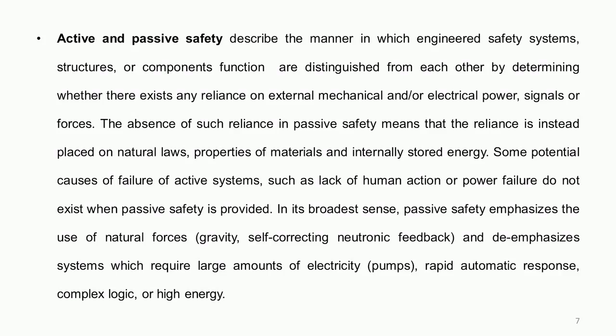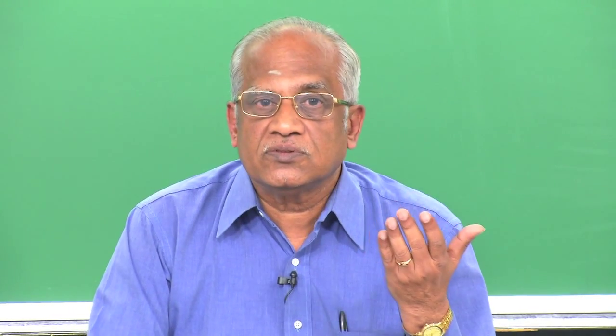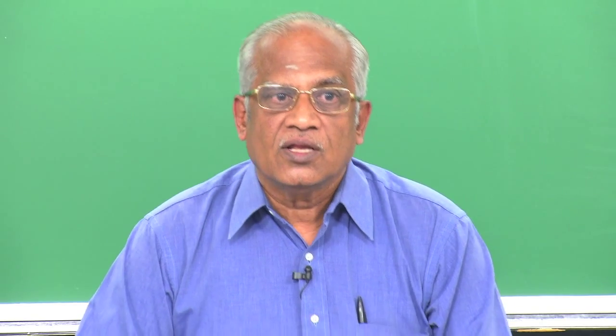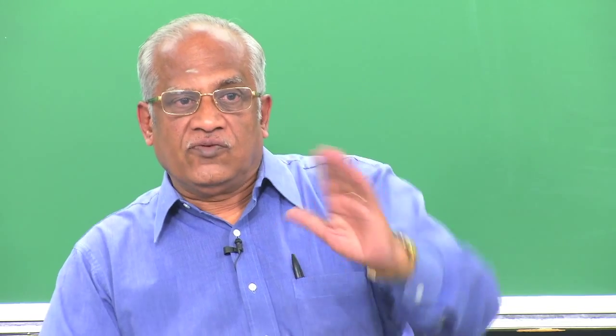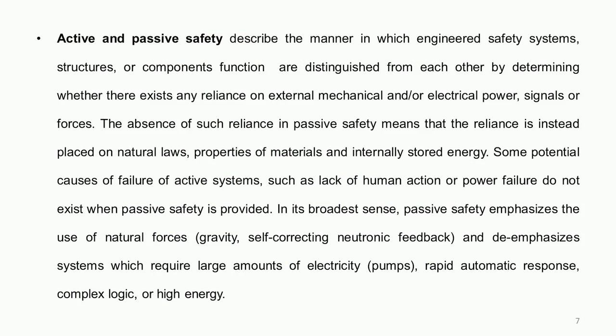A passive safe system basically works on natural forces like gravity. In neutronics, you have a negative feedback system — if the temperature or power goes up, the feedback effects oppose the increase in power so that the power gets reduced and eventually the temperature also gets reduced. It doesn't involve systems requiring large electrical systems like electrically-driven pumps or complex logic or high energies. Passive systems do not rely on external sources of power or signals.